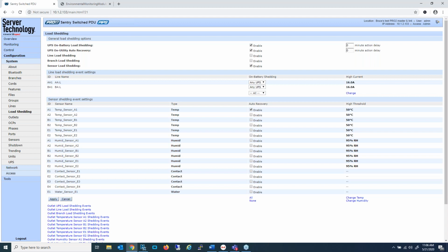equipment downstream. So with this knowledge, we decided we could automate some power control features with the intent to be that when a UPS loses utility power, we can then switch off pre-selected outlets so as to increase the runtime for critical gear. So the idea is that you shed the load of non-critical gear so that the batteries in the UPS systems will last longer for critical gear. That was the original purpose for load shedding. We've vastly expanded the load shedding capabilities beyond just reacting to a UPS on battery condition. But let's start by looking at that original concept.